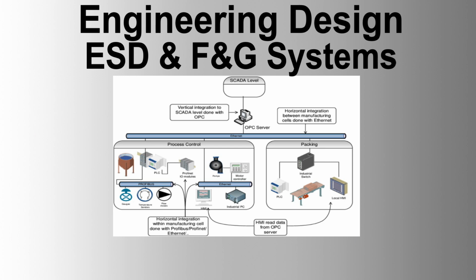Power supply monitoring. 1. Status monitoring. The ESD F&G system must include monitoring features to continuously check the status and health of the power supplies. Alarms must be generated for any power supply faults, including voltage irregularities, overload conditions, and UPS battery status. 2. Integration with ESD F&G system. Power supply status must be integrated into the ESD F&G operator interface for real-time monitoring and diagnostics. Detailed event logs for power supply failures and recoveries must be maintained for analysis.